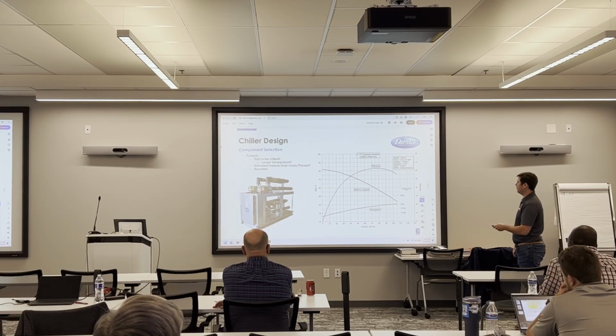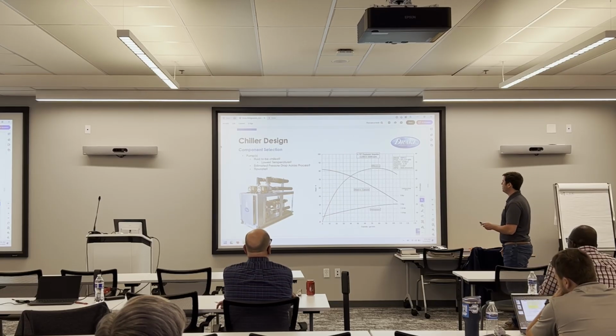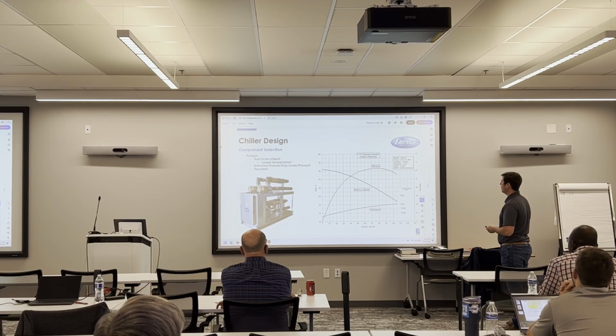So it's pressure versus gallons per minute. And this one sloping up through the top is our efficiency curve. If I'm picking a pump, I want to make sure it falls right on the cusp of this efficiency line. That gets you your best bang for your buck. I'm not going to pick this pump if they said they want something that does 10 GPM at 40 feet of head, because in terms of efficiency, we couldn't be any lower. And I also don't want to pick a pump that does 100 gallons per minute at 45, 46 feet of head.